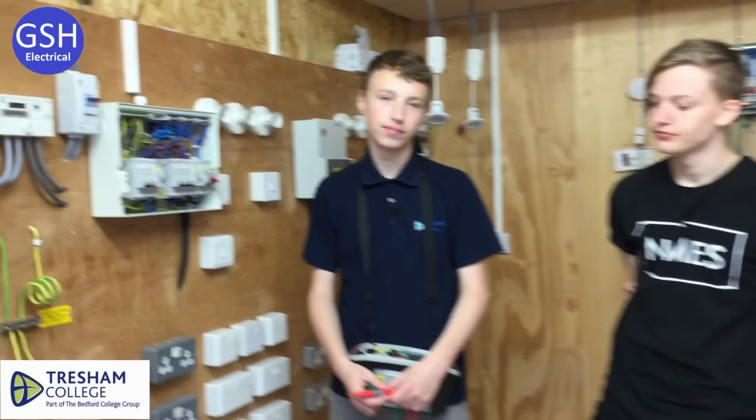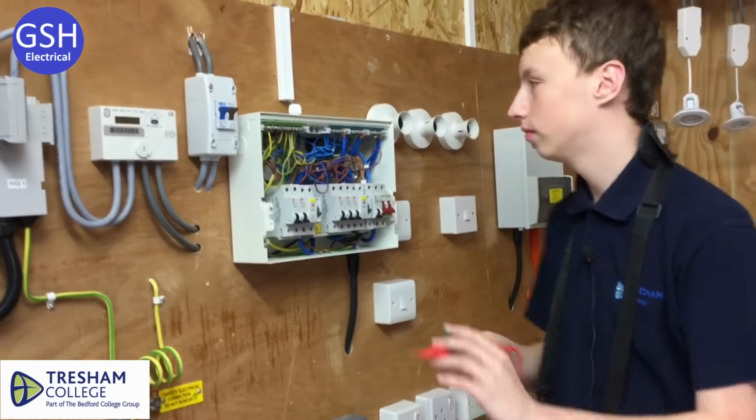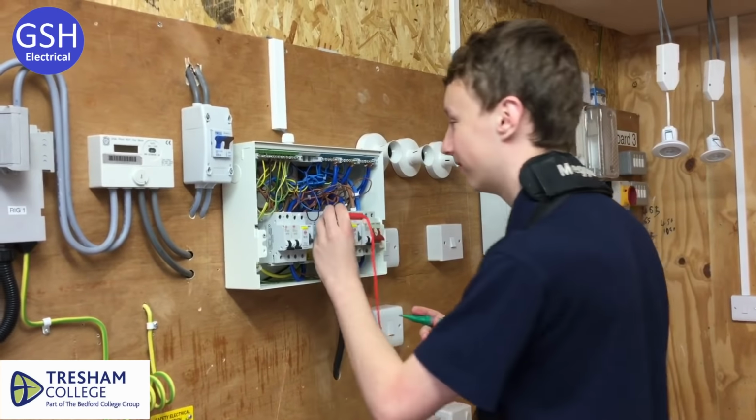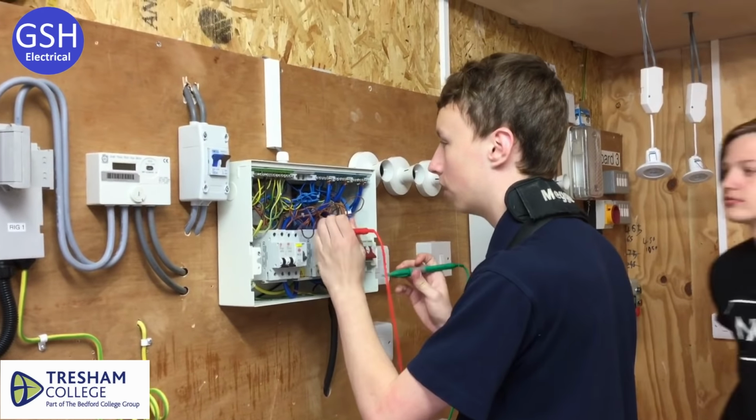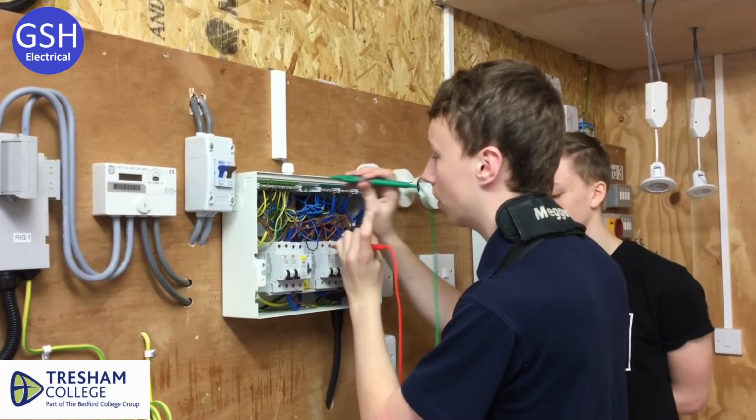Okay, which test are we now carrying out, Harrison? Insulation resistance. Good. And what voltage are you going to pass through the circuit, Logan? 500. AC or DC? DC. The smallest acceptable value of insulation resistance, Harrison? 1 mega ohm. Okay, let's do this test. The switches are two-way in this circuit. In which position did you leave them? On. Okay. And as Logan goes into the board, which is a complete mess because of our level 3 learners, he's going to carry out our insulation resistance test for us.